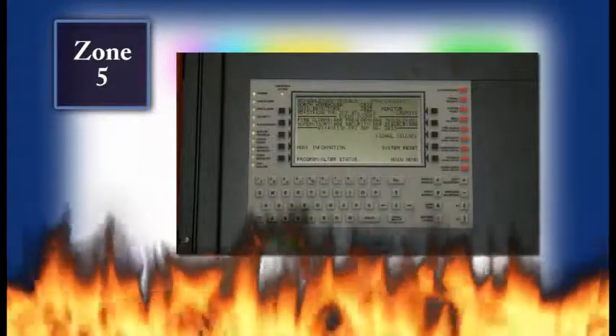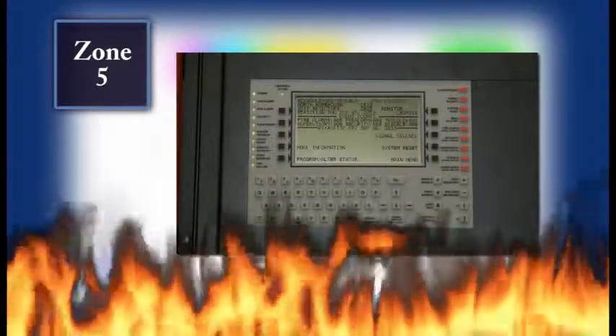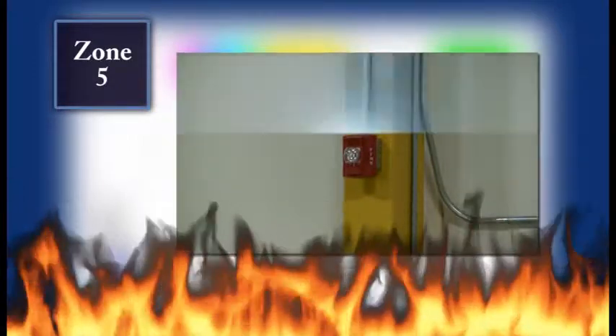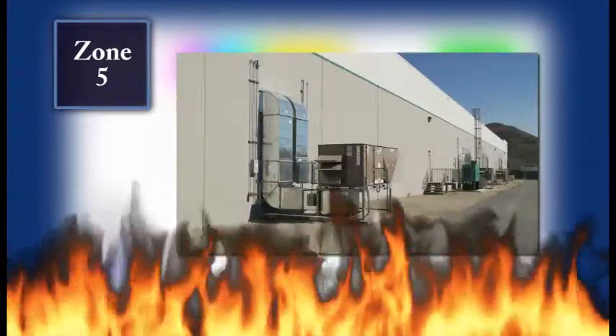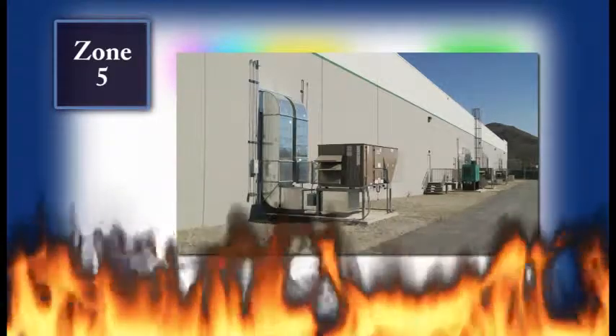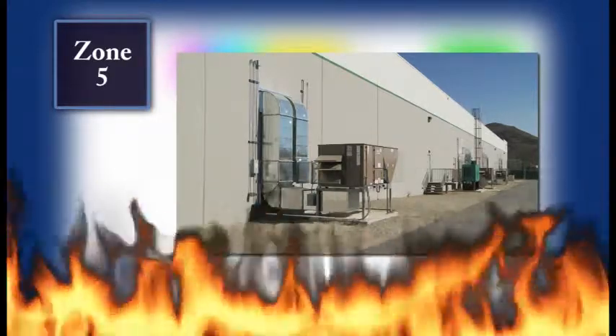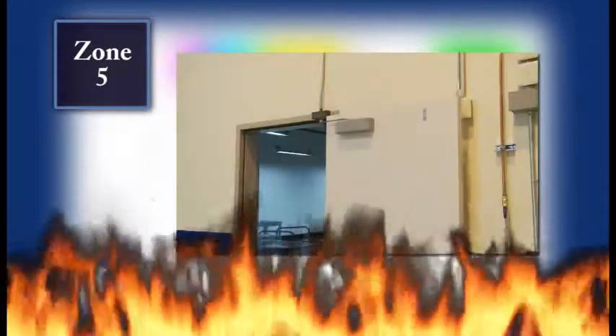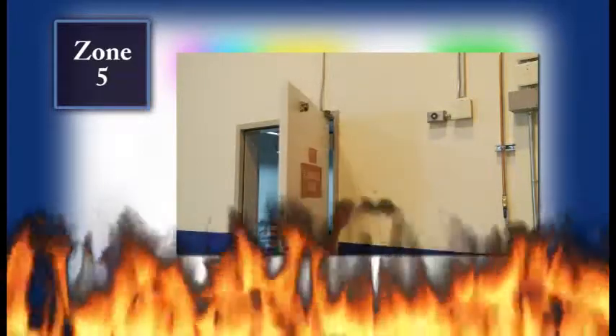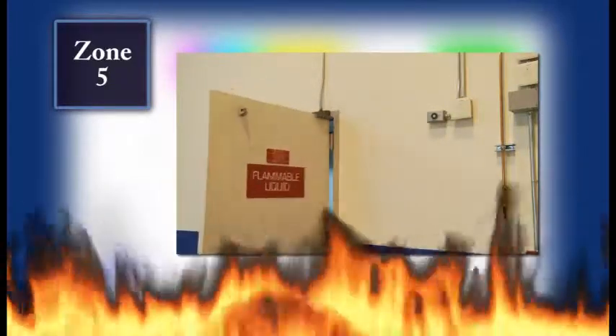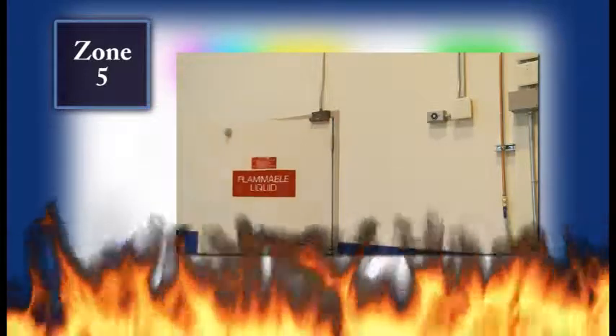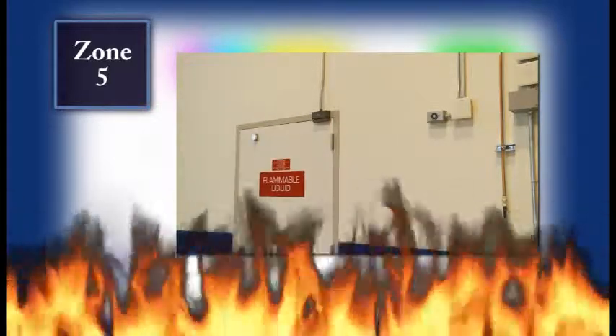The associated zone shall be annunciated on the fire alarm control panel. Horn strobe devices shall operate throughout the facility. HVAC units serving the entire building shall be de-energized and fire and smoke dampers shall close. The magnetic door holder and other similar devices shall operate, resulting in door closure of all hazard room doors through the fire alarm control panel.